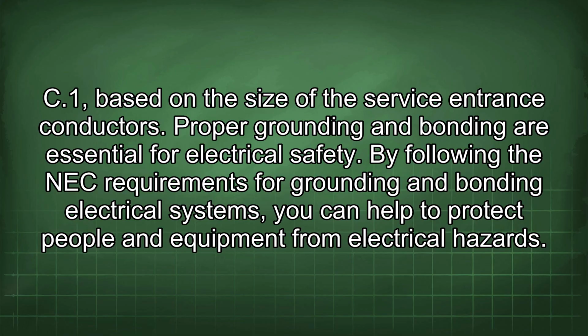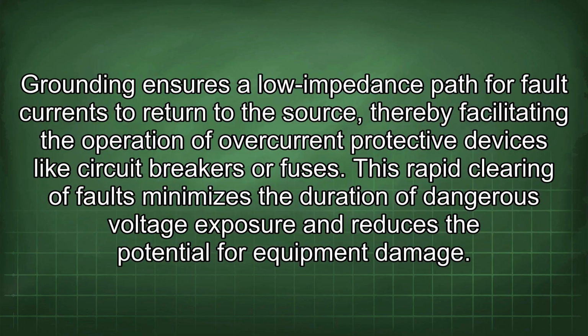By following the NEC requirements for grounding and bonding electrical systems, you can help to protect people and equipment from electrical hazards. Grounding ensures a lower impedance path for fault currents to return to the source, thereby facilitating the operation of overcurrent protective devices like circuit breakers or fuses. This rapid clearing of faults minimizes the duration of dangerous voltage exposure and reduces the potential for equipment damage.